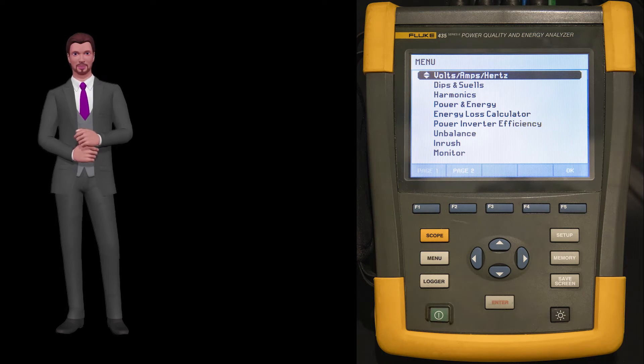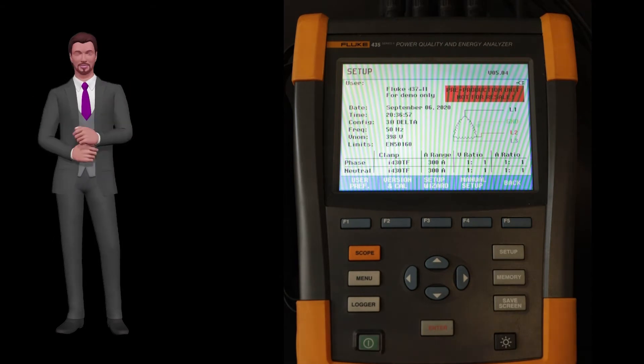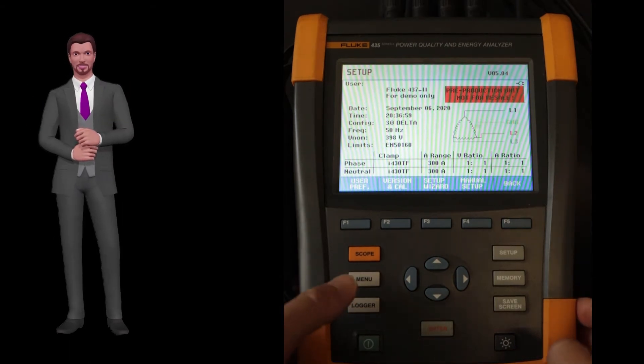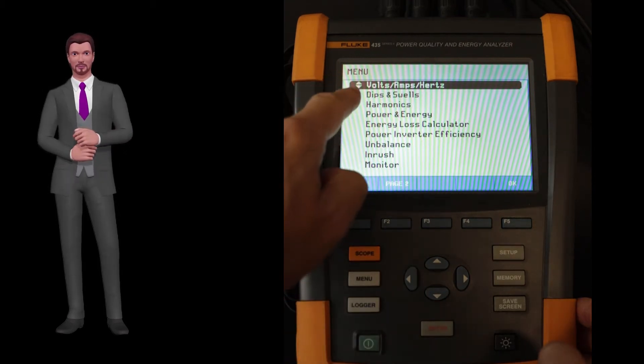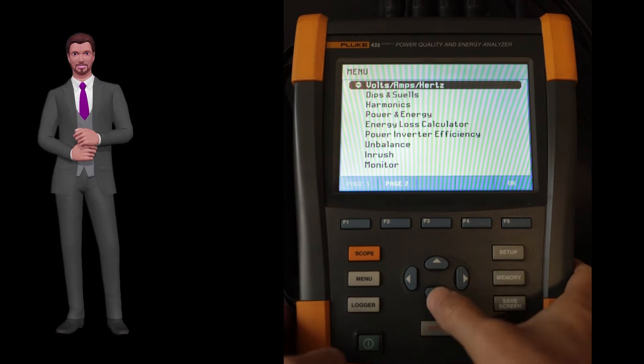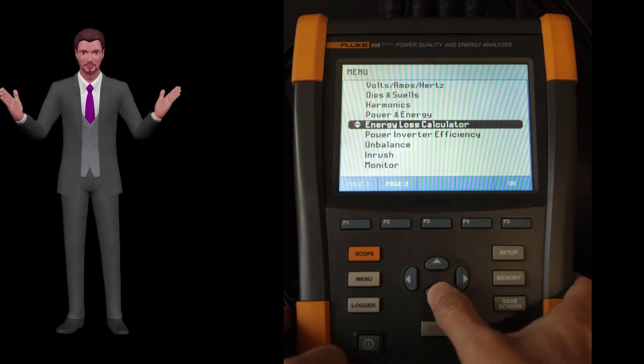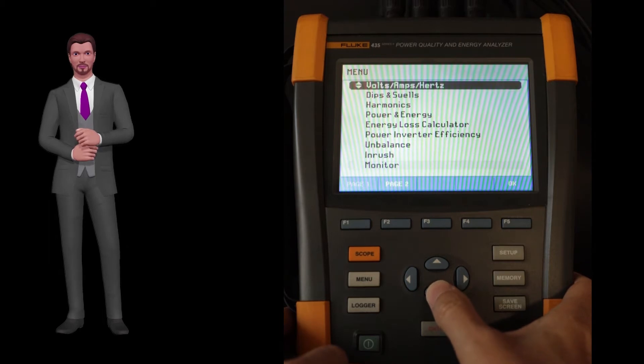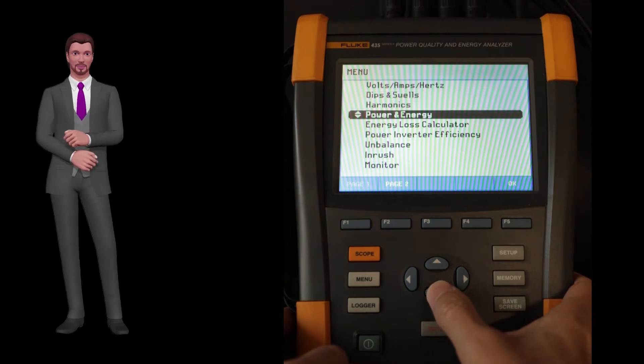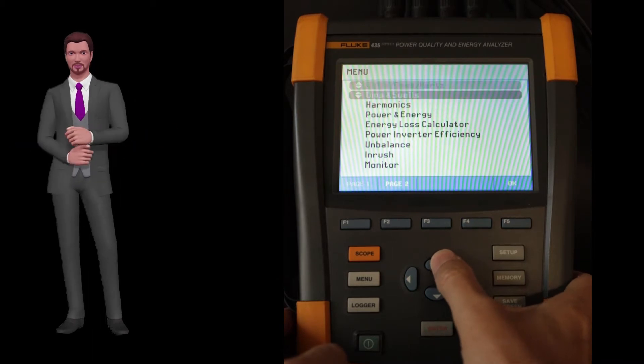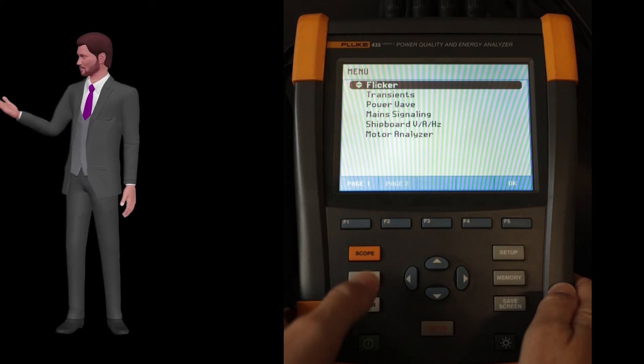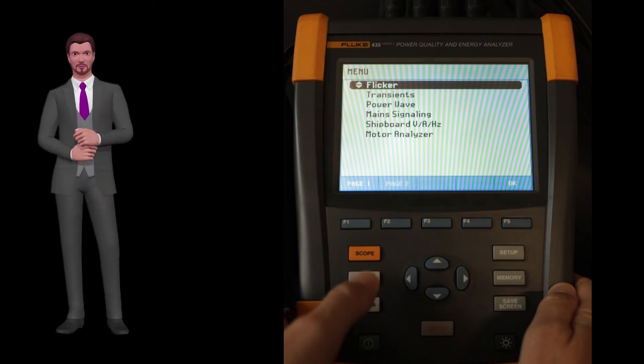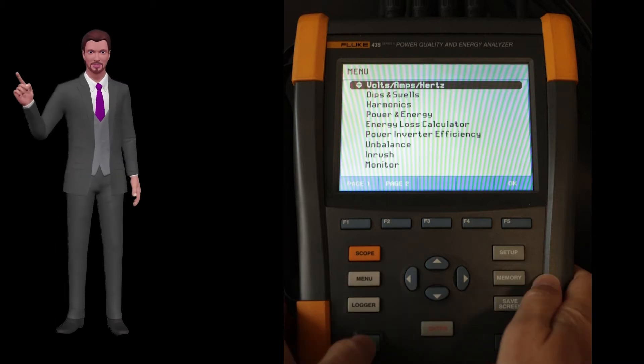For that, we turn on the unit and press the menu key, and as you can see, the word menu appears at the top of the screen to indicate that we are precisely in this option. Below, there are 9 lines with the different measurement functions. With the up and down arrow keys we can move over these measurement functions. Below the list, there is a blue area showing Page 1 over the F1 key, Page 2 over the F2 key, and OK over the F5 key. With F1 and F2 we can alternate between two different sets of measurements. Once the function that interests us has been selected, with F5 we accept the selection.